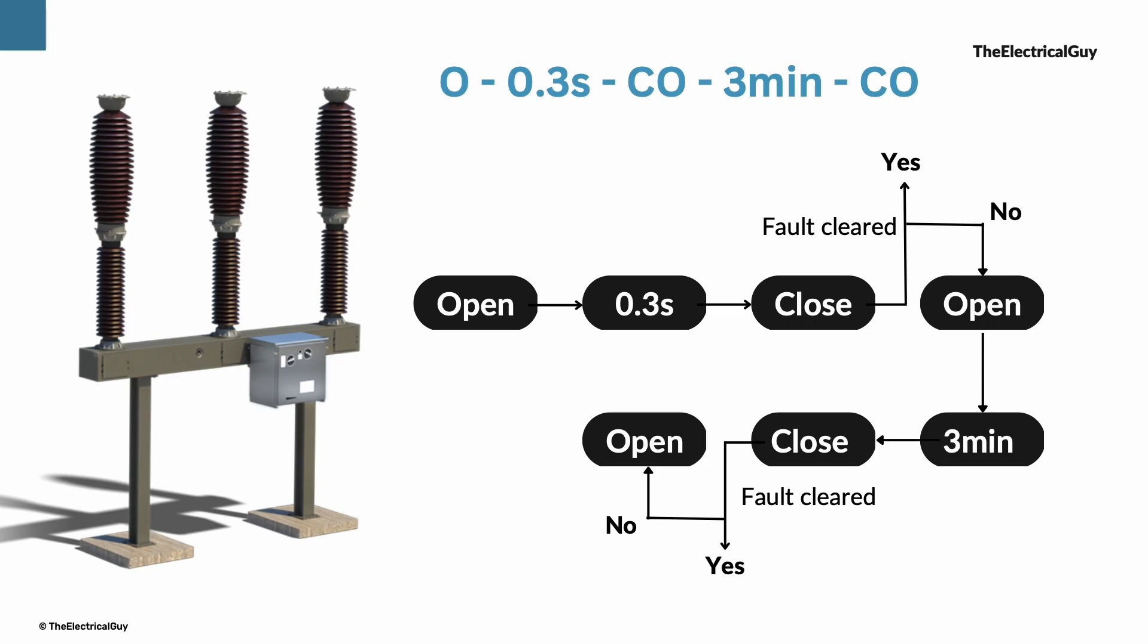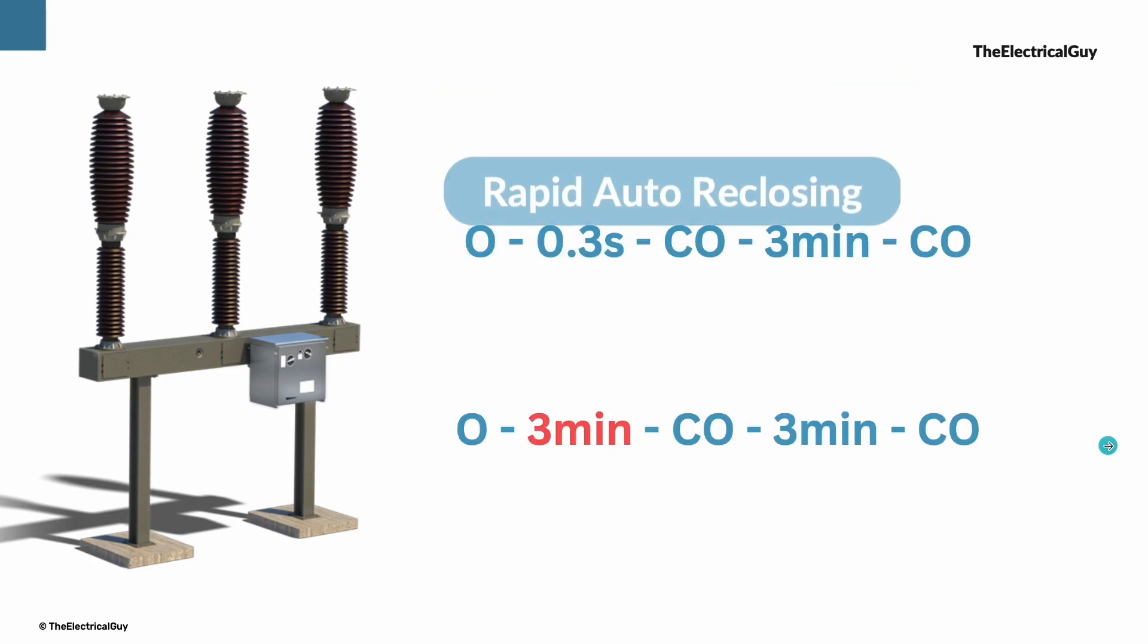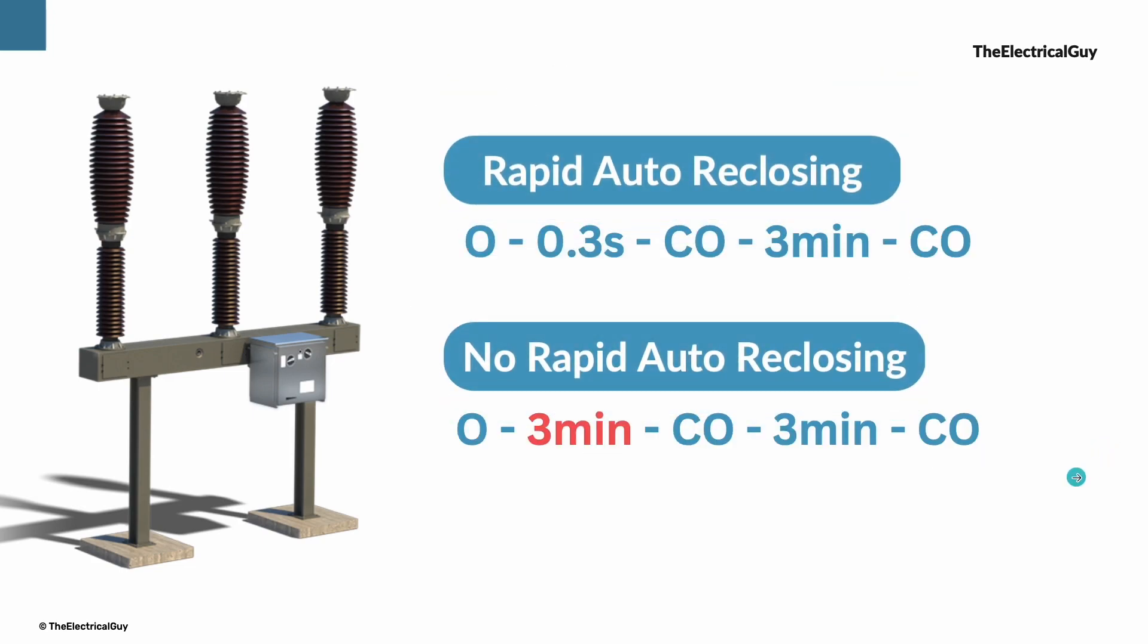Now the duty cycle that we saw was meant for rapid auto reclosing. There is another variant in this which you can see on your screen. The only change is that instead of 0.3 seconds, it is now 3 minutes, and this duty cycle is not meant for rapid auto reclosing.